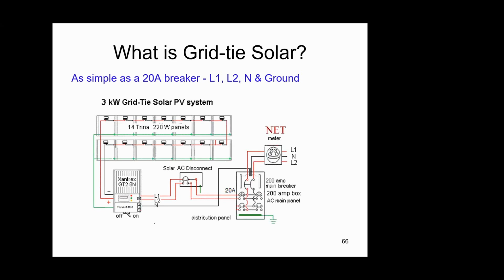So what is grid tie solar? Grid tie solar simply says you take all these 30-volt solar panels and hook them in series, and that gives you a supply voltage of anywhere from 300 to 550 volts in series at about 8 amps. That's just 2 wires going into your grid tie inverter. The reason you hook them in series is to save copper: you bump up the voltage and the current stays the same, so you can use number 12 or even number 14 house wiring for your solar distribution.